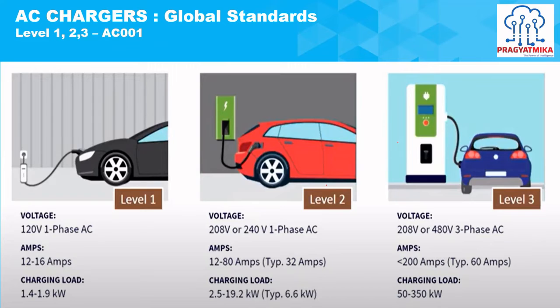So the three levels that we have: majority for the single phase, we have the 230 volt single phase, 15 ampere supply, which can take a load of up to 3 kilowatt generally for home purpose. But if you are doing it in public charging infrastructures, it can go up to 32 amperes of range, and you can handle up to 20 kilowatts of charging load.